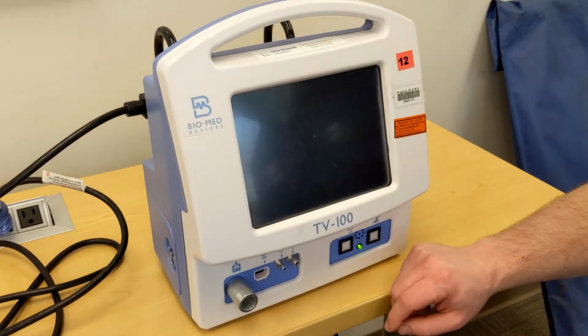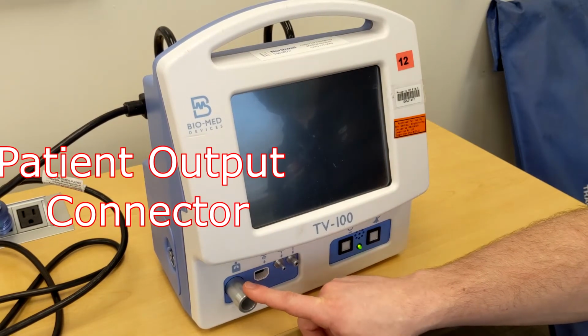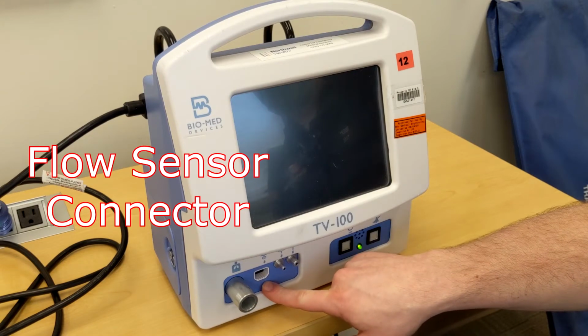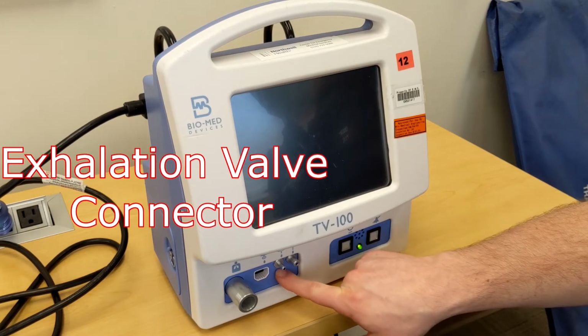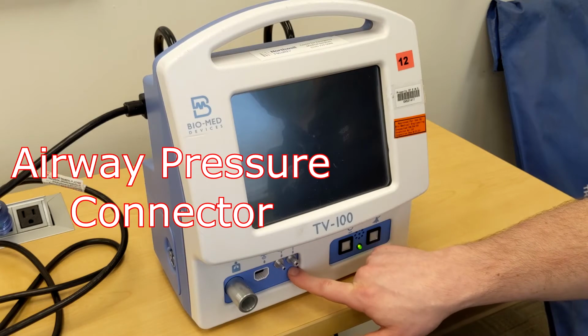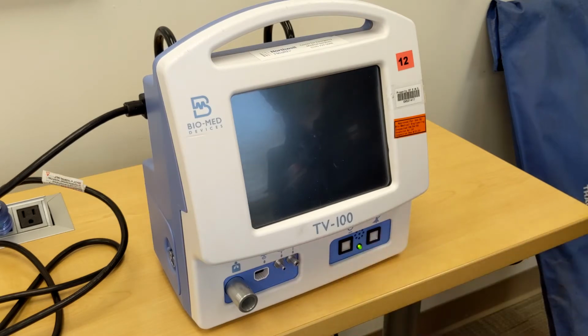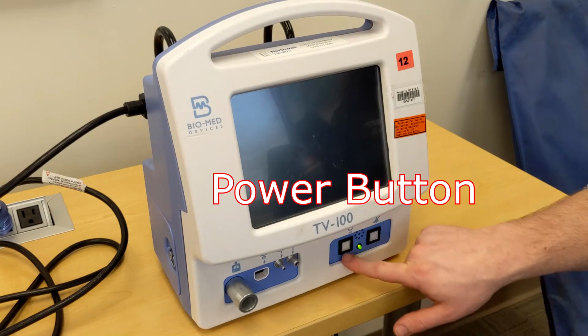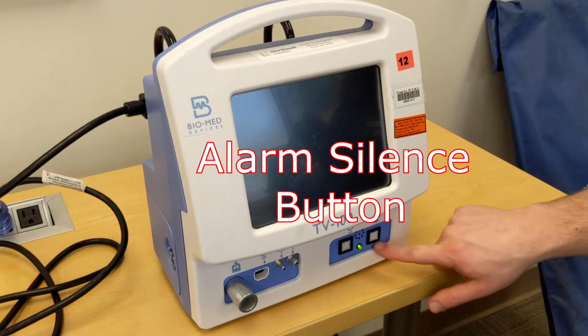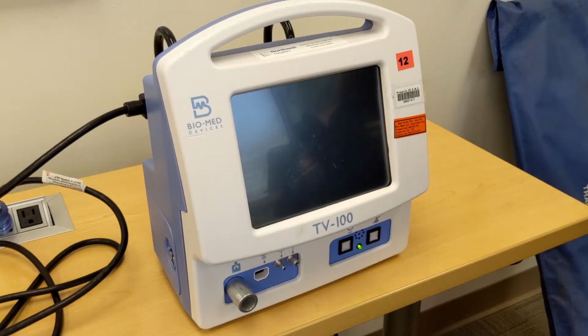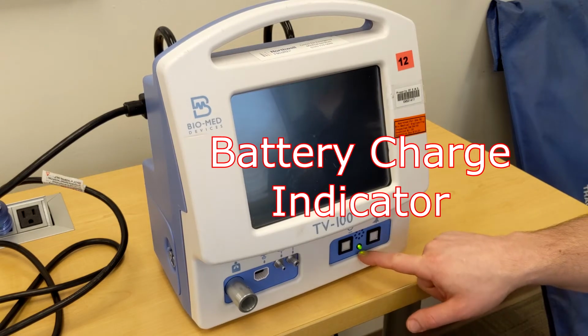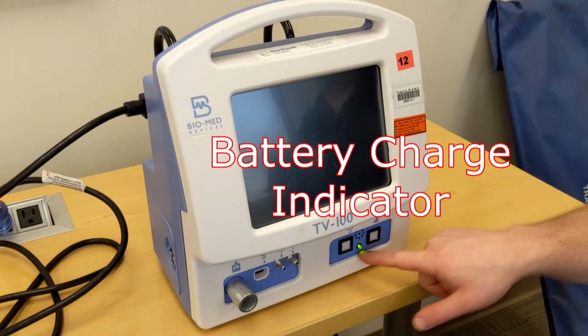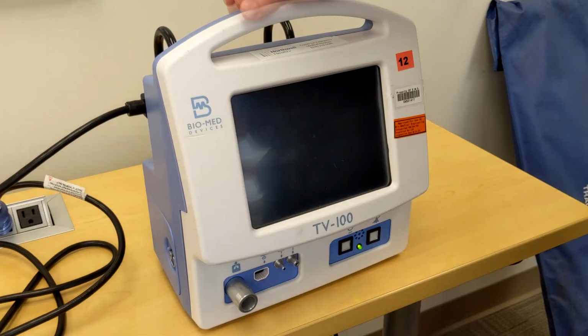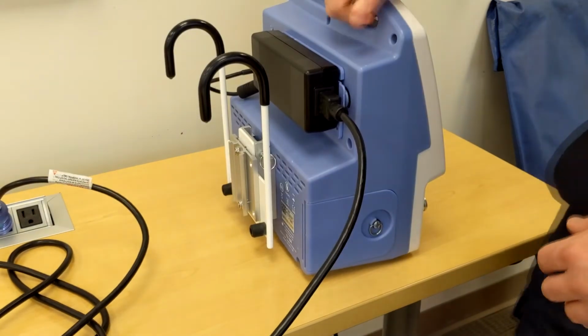On the front of the ventilator, we have the patient output connector, flow sensor connector, exhalation valve connector, and the airway pressure connector. On the bottom right, we have the power button and the alarm silence button. This bulb located here is the battery charge indicator. Rapid blinking of the battery charge indicator LED indicates a problem charging and should put the ventilator out of service.